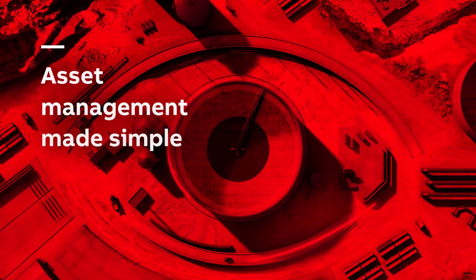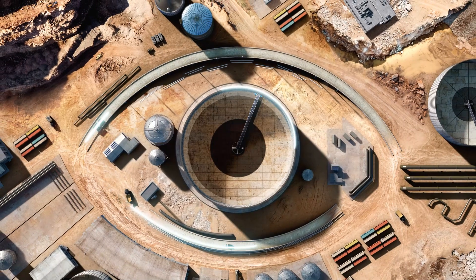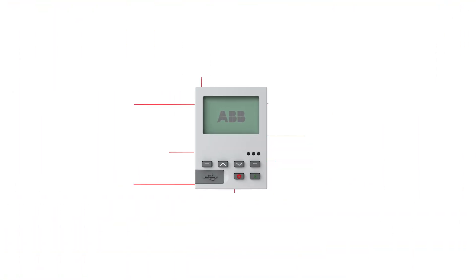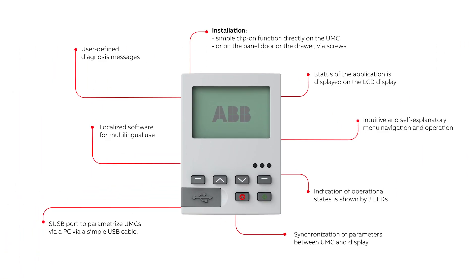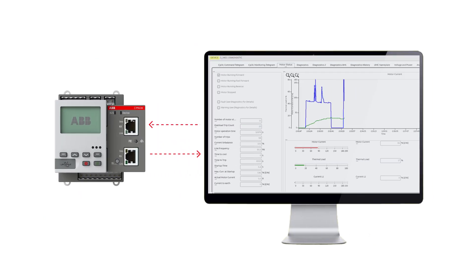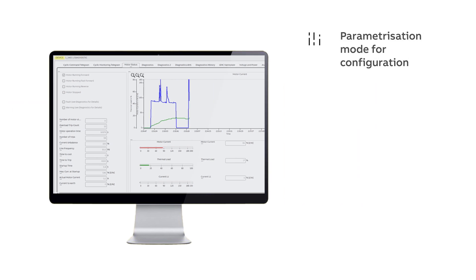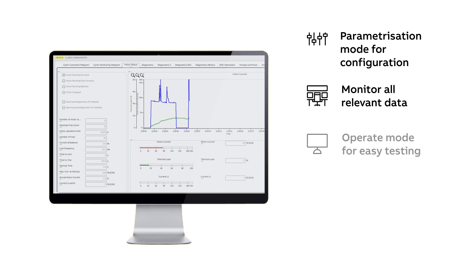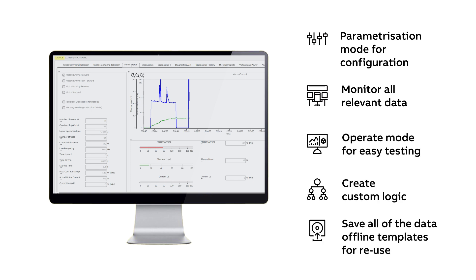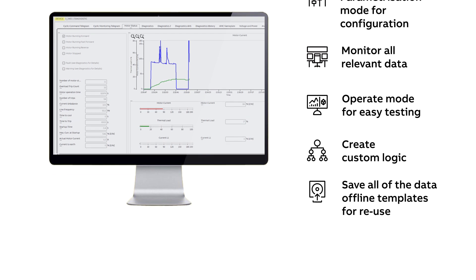Simplify asset management with the UMC's user-friendly configurations, offering unique local control with numerous functions, software configuration by the PLC, LCD display, and the Field Information Manager. The FIM UMC software handles parameterization, monitors measurement and diagnostic data, provides an easy testing mode, allows for custom logic creation, and enables offline data template storage for reuse.